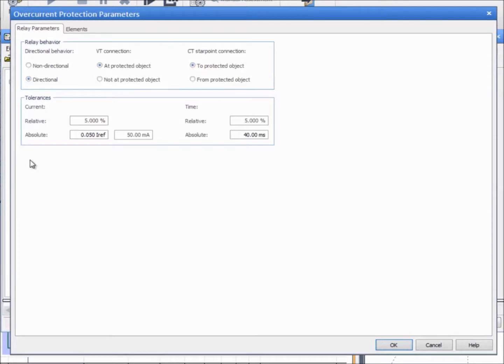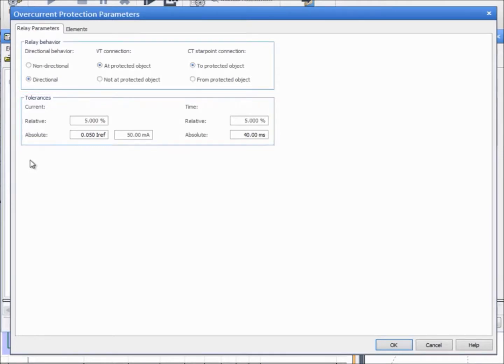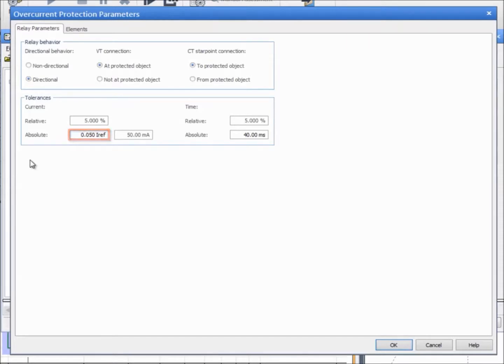Enter the current and time tolerances according to the relay's manual. These tolerances can be defined as either absolute or relative values. Relative is a percentage of the setting value. Absolute is a constant value that is defined as a multiple of the reference current. The reference current is linked to the nominal current by default.